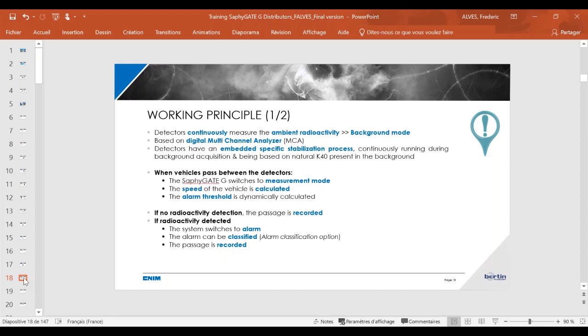The detectors also have an embedded specific stabilization process continuously running during the background, and based on the potassium present in the background. That's why it's really important, when you do some tests close to the system, to not irradiate the system during its stabilization phase, or to not irradiate the system without masking the cells, for sure.